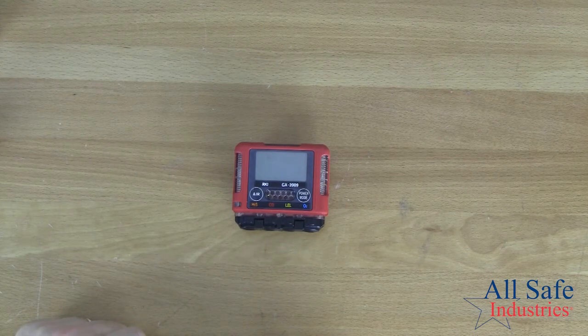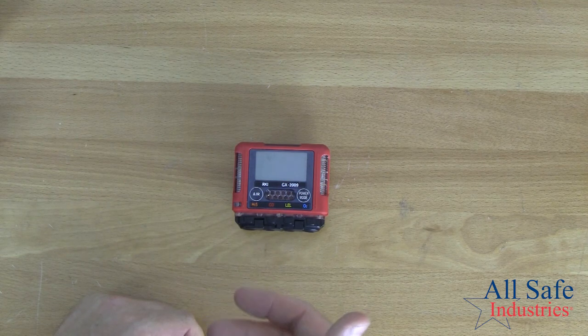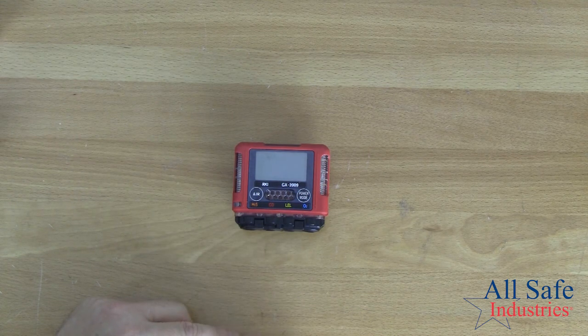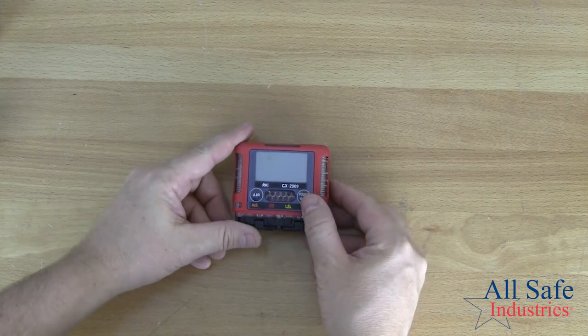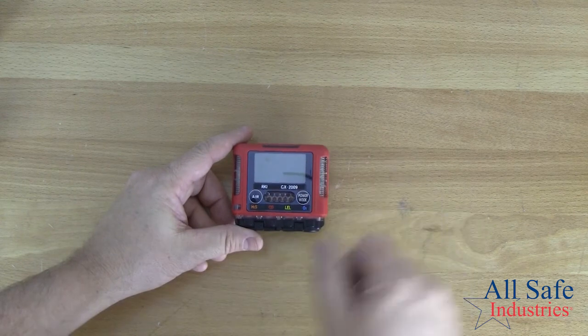All right, now I'm going to show you how to calibrate the GX-2009. So why would you calibrate? Well, if your instrument tells you that you've exceeded the 90 days, there's a good clue that you need to calibrate. And the instrument will actually go into alarm to remind you that you've exceeded your calibration limits. Let me show you that.